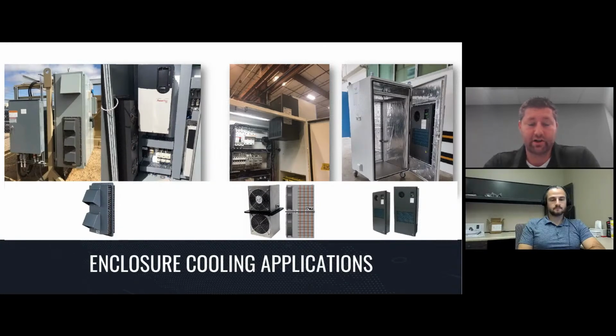The second one in the middle is our heat pipe cooler. On the bottom of the picture you can see a cross section of the heat pipe cooler, the HPC, and in the copper color you can see the heat pipes shown. These are simply straight heat pipes using methanol as the working fluid, transferring heat from the hot air inside the cabinet to the cooler air outdoors. Heat pipes, as we'll get to in a couple slides, are an extremely efficient mechanism for transferring heat, able to transfer at a very low delta T, driving down the footprint of cutout needed on the cabinet. The example shown is going onto an electronics enclosure in a machining factory that's driving the machinery.